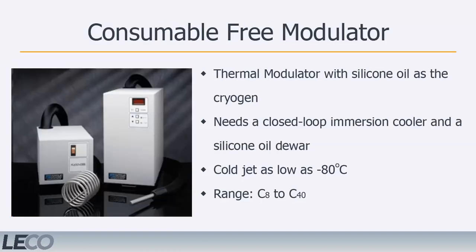LECO also offers the consumable-free thermal modulator system, which does not require liquid nitrogen as the cryogen. In this thermal modulator option, the dewar of liquid nitrogen is replaced by a dewar of silicone oil. The silicone oil is chilled by a cold probe from a closed-loop immersion cooler. Electronic control options specific to the consumable-free thermal modulator include the ability to set the chiller to specific temperatures as low as negative 80 degrees Celsius. Because this modulator does not reach the same minimum temperatures as liquid nitrogen, it is recommended for analyzing compounds with a volatility range between C8 and C40.